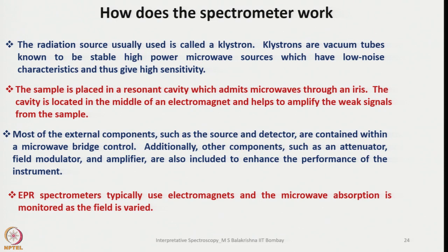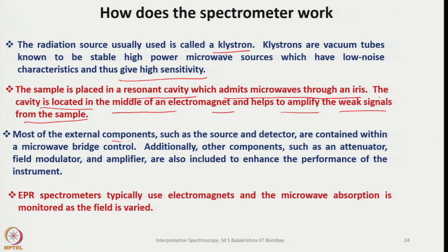The radiation source usually used is called a klystron. Klystrons are vacuum tubes known to be stable, high-power microwave sources with low noise characteristics, giving high sensitivity. The sample is placed in a resonant cavity between the magnets, which admits microwaves through an iris and helps amplify weak signals from the sample. External components such as the source and detector are contained within the microwave bridge control, and additional components such as attenuator, field modulator, and amplifier are also included to enhance performance.